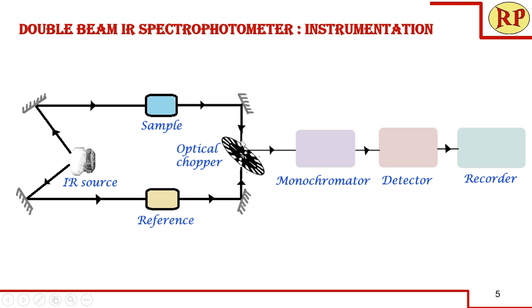For each frequency, the sample and reference beams go alternately into the monochromator. The monochromator is not a simple prism as seen in other spectrophotometers — it is a complex component containing a prism or grating, slits, mirrors, and filters. If a prism is used, we normally use NaCl or KCl prisms. The role of the monochromator is to disperse the polychromatic light coming out of the sample and reference into individual frequency components.